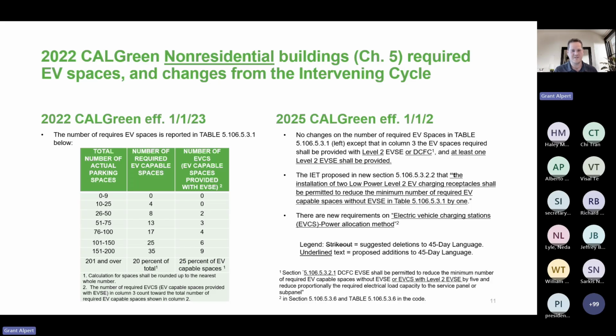There's also this whole new method for calculating how many charging spaces need to be installed, called the power allocation method, which is a new requirement. It's an alternative to the table where you look at the number of spaces and see, for example, that there need to be 13 EV capable spaces for a 51 to 75 space parking lot. With this method, you take the number of spaces and multiply it by a power number, and then you can divide that power however you want. I'll show that a little later.